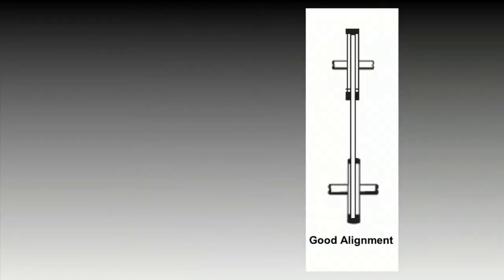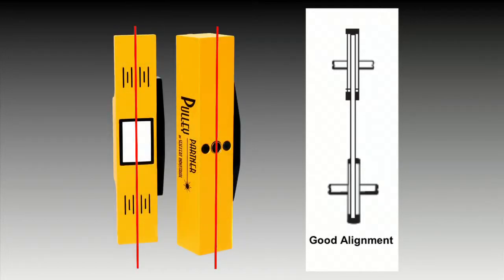Good alignment is achieved when the transmitter laser line and the corresponding reflected laser line coincide with the black reference lines on the reflector and laser transmitter, respectively.